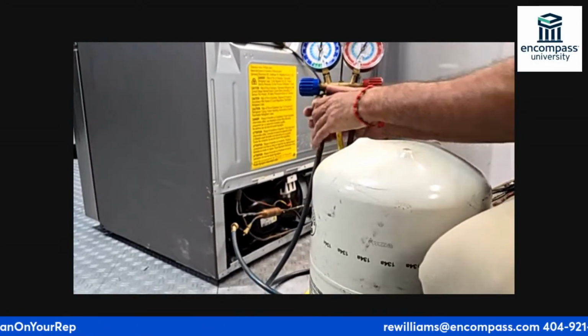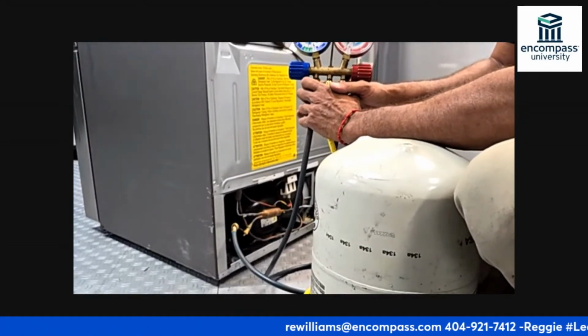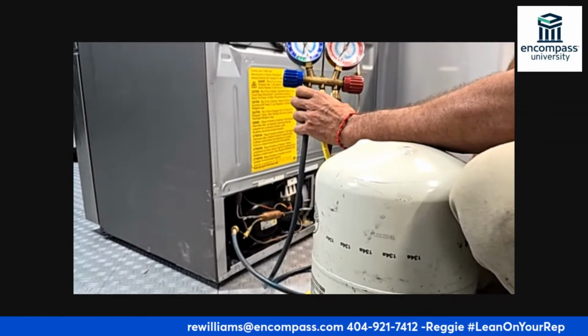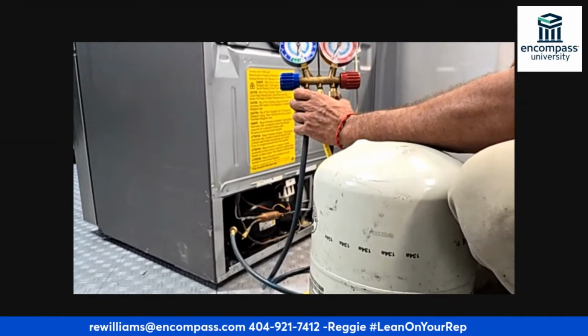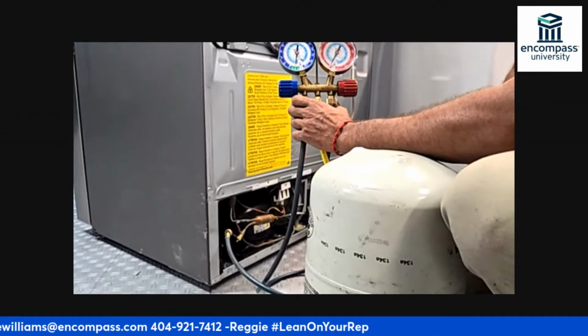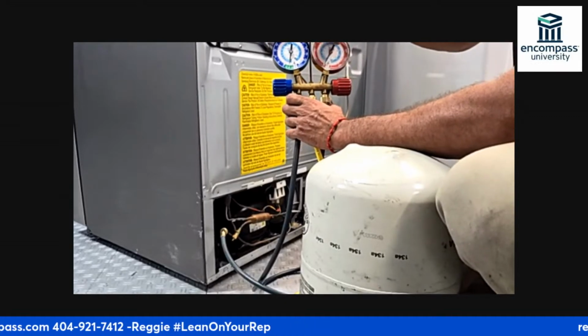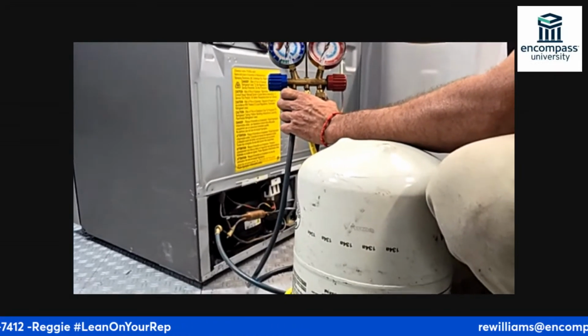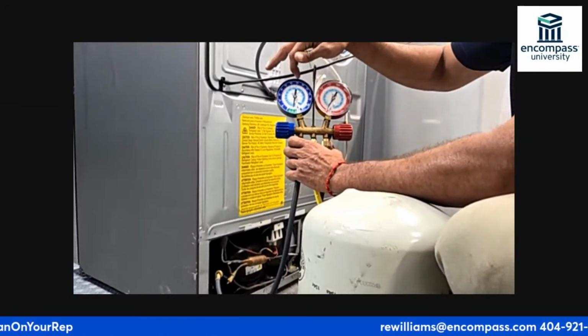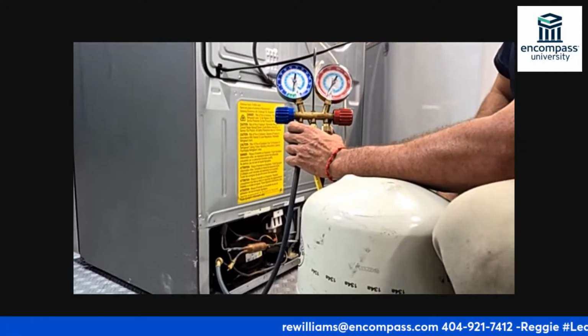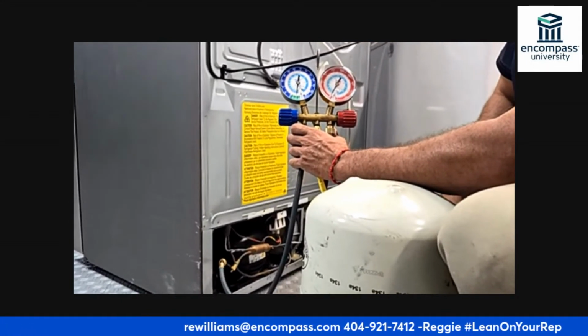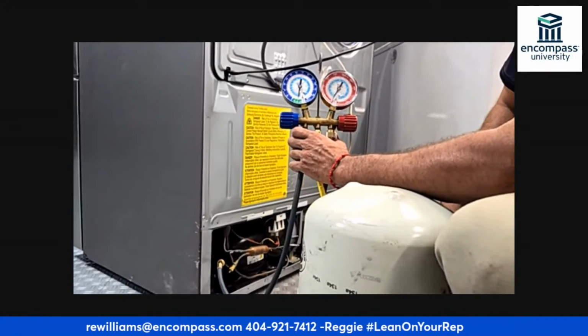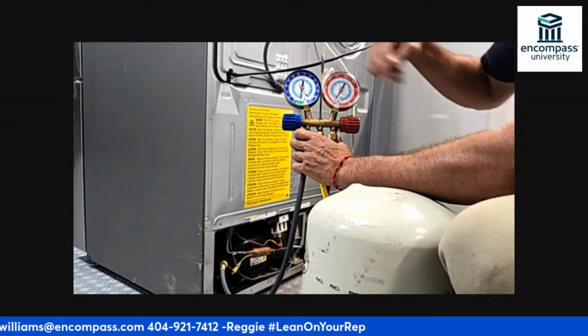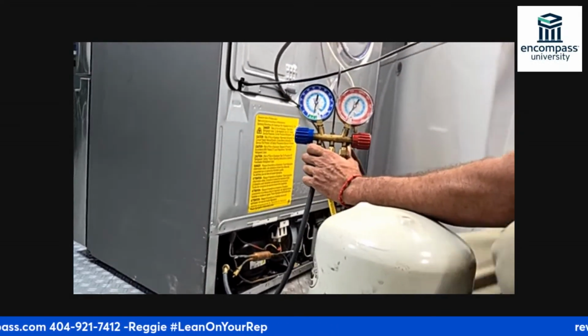One way to tell, and this is where I'll end the class without getting too much into sealed systems, is we're going to do what's called stabilization. We're going to unplug the unit, and when we do, it should go back up to this area, 60, 70 PSI, and it should do that relatively without any problems. So I'm going to unplug it now and see how long the needle takes to move.